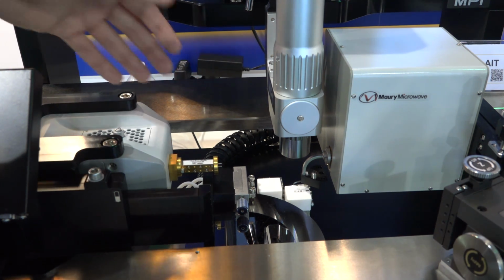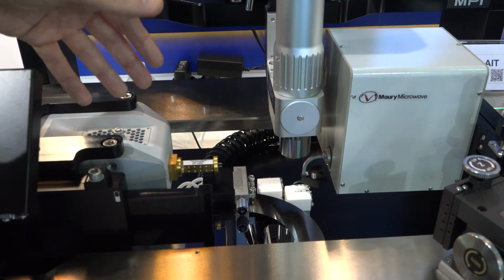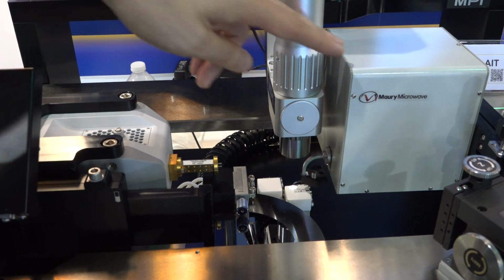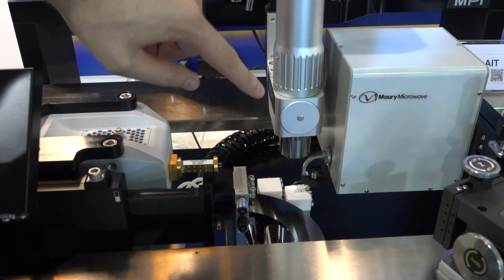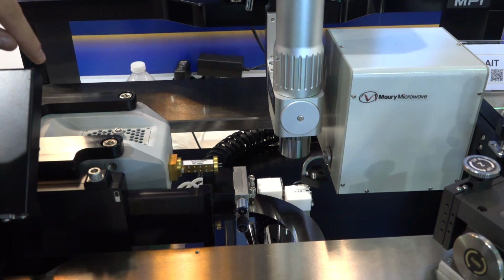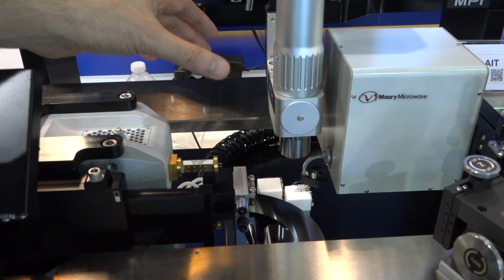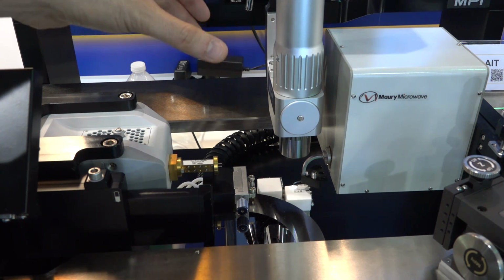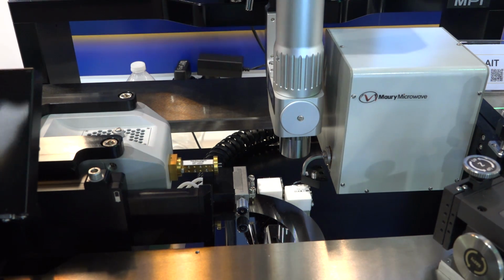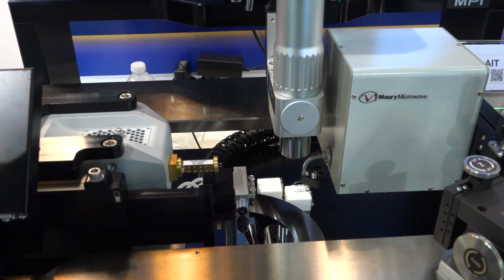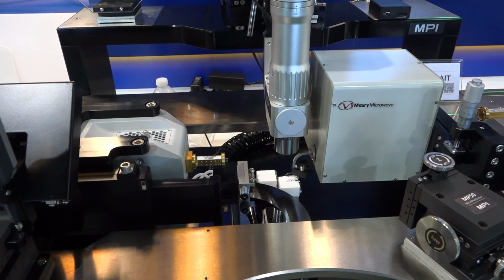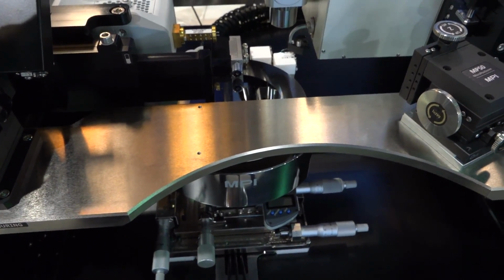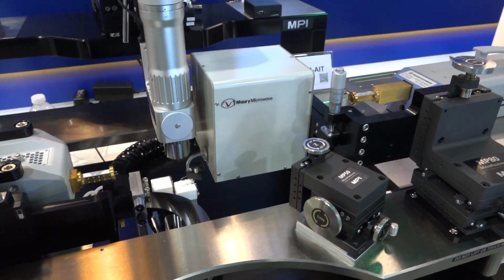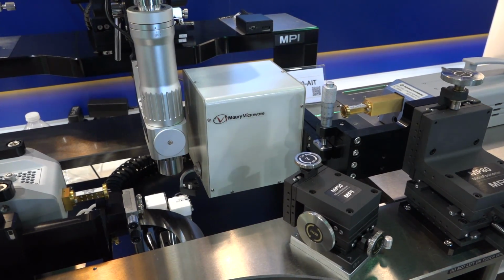By eliminating the bends, by designing this to be so close to the device under test, you can even do load pull measurements without anything other than a direct connection to a probe. You can see right there a waveguide probe directly connected. The microscope has a very narrow design there, which has a long working distance, allowing you to come very close. And these things can be quite beneficial at terahertz and millimeter wave frequencies because you really don't have dynamic range to play around with. The flexibility of this probe station is really, really nice and gives you an idea of what you can do if you design a probe station from the ground up for millimeter wave applications and terahertz applications directly.